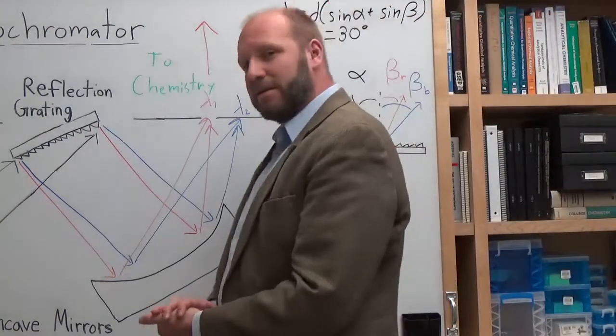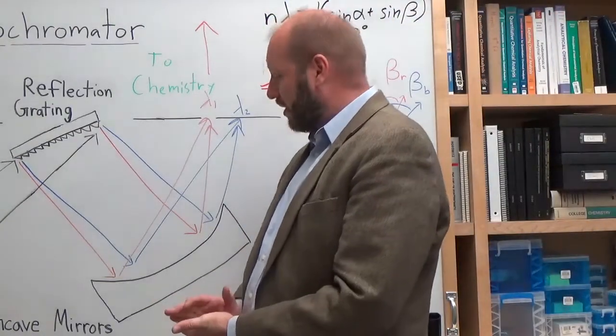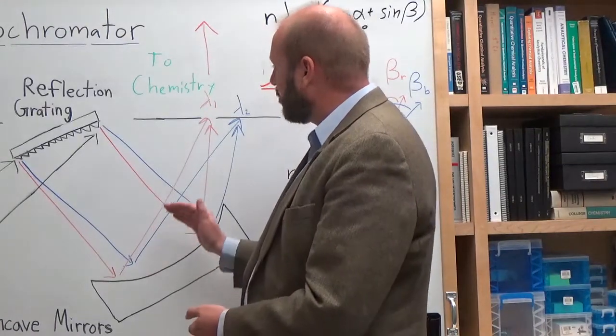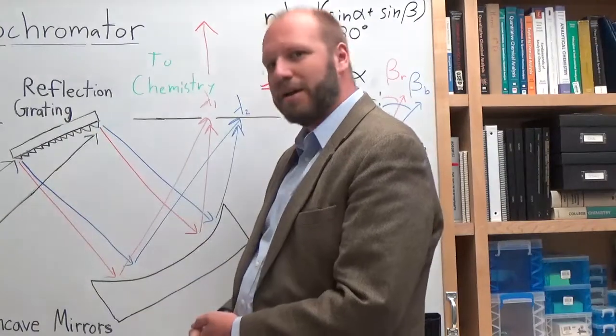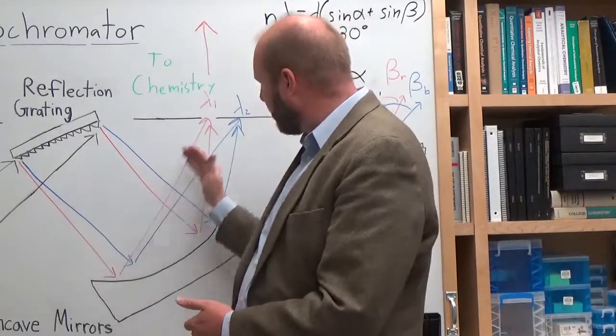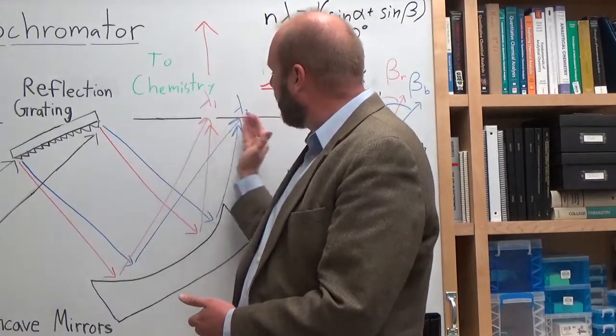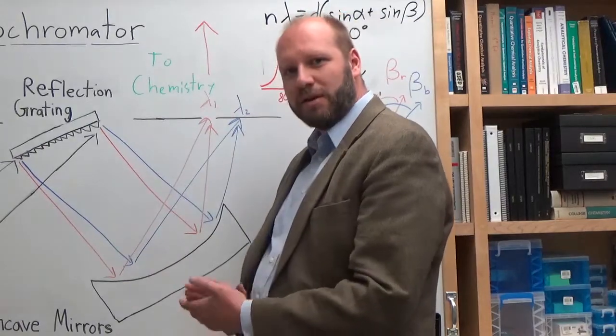So to generate an instrument that can select a different wavelength, we can then change the incident angle by rotating this diffraction grating. What that does is focus the light at different points on the exit slit so that we can control the wavelength of light that will hit it and then go on to do chemistry.